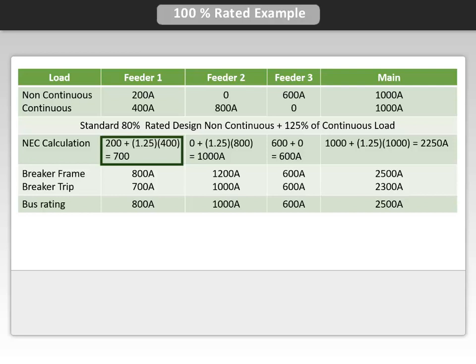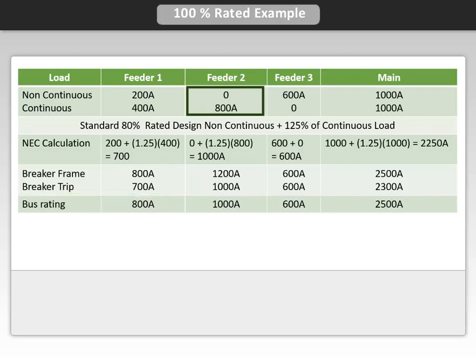Since 700 amps is not a standard frame, we need to use an 800 amp frame with a 700 amp trip. Feeder number 2 has an all-continuous load of 800 amps. When we take this load times 1.25, we have a required rating of 1,000 amps.